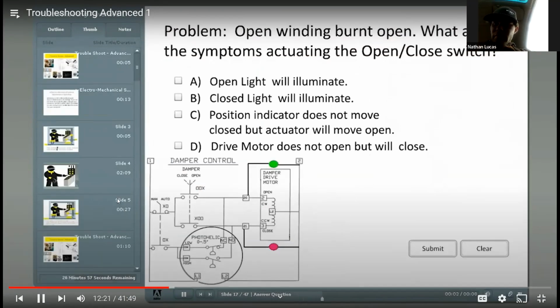The open winding burnt open. What are the symptoms when actuating the open-close switch? Okay, David, pick somebody. All right, Isaac. The open winding under the damper drive burnt open. So what are the symptoms when we try to open or close? Will the open light illuminate? You're muted. Will this light come on if we try to open it?